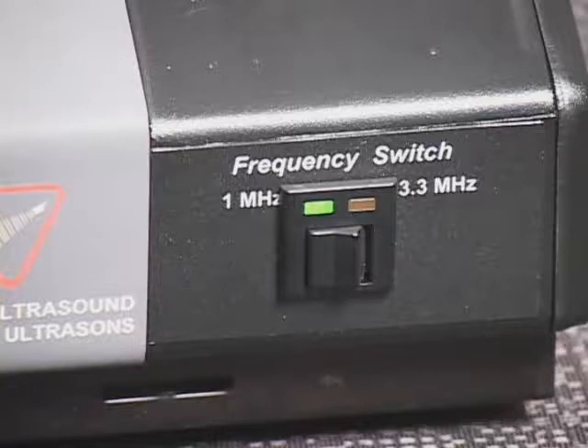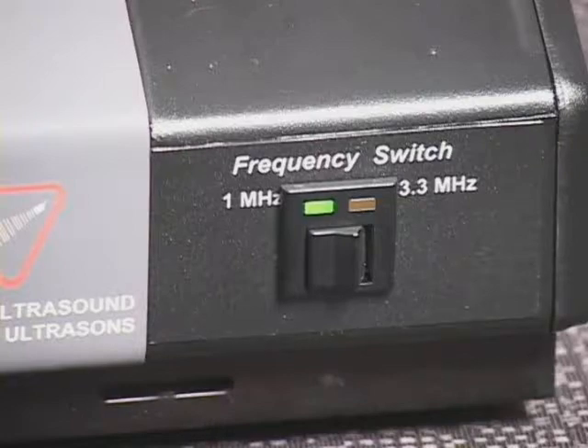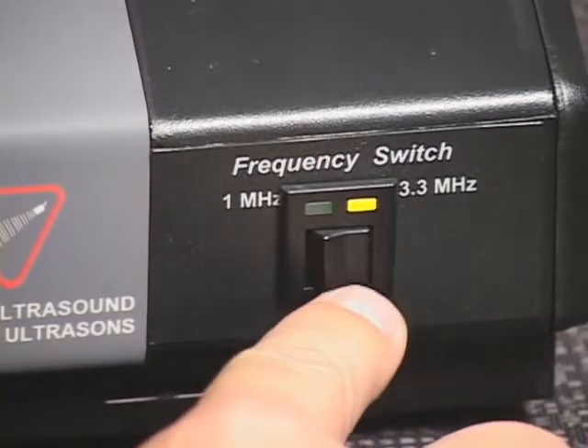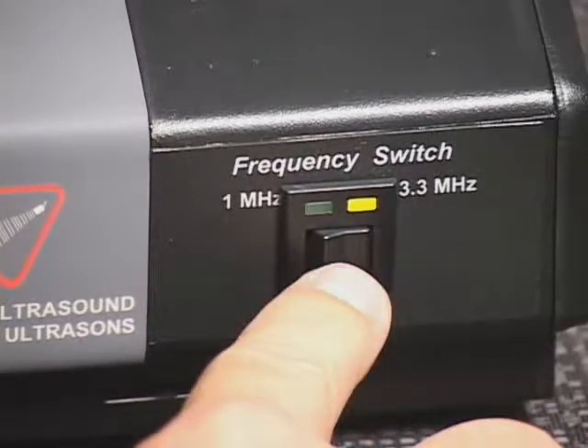When the ultrasound frequency switch is in the left 1 MHz position, the green ultrasound frequency indicator light located on the upper left corner of the ultrasound frequency switch bezel will illuminate and ultrasound output frequency of 1 MHz is selected.